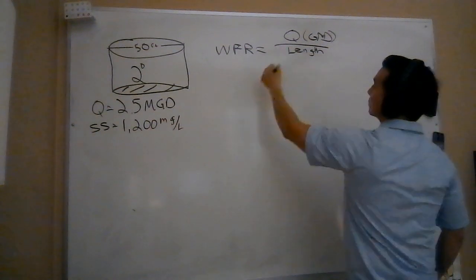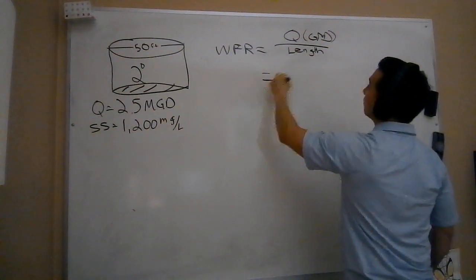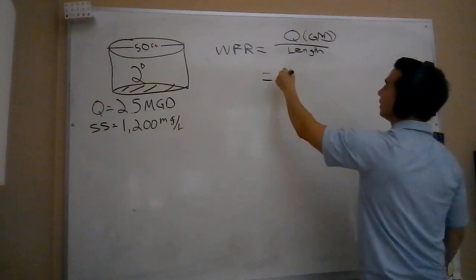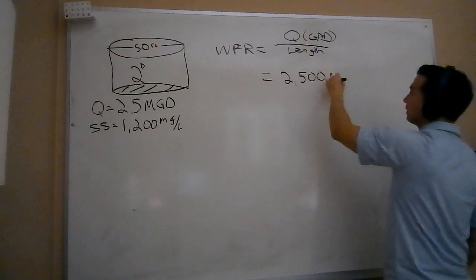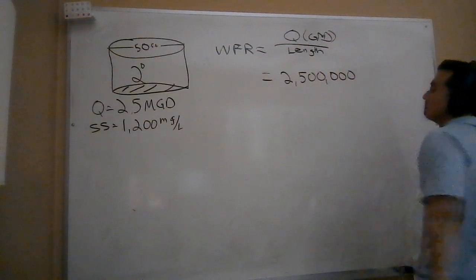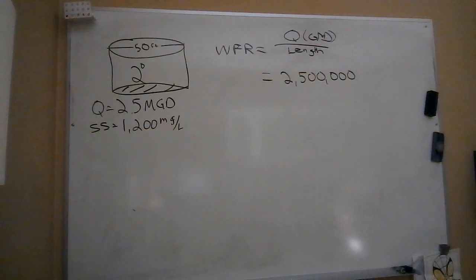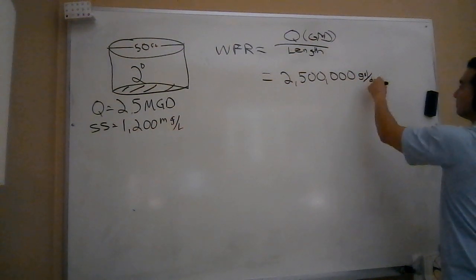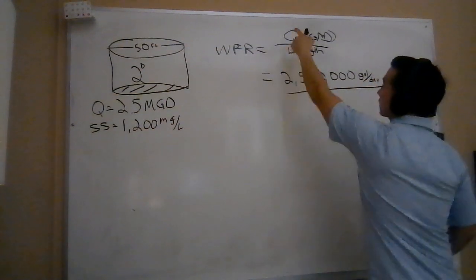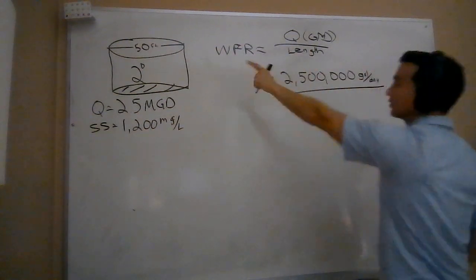My flow rate Q - I've already given that here - is 2.5 million. We're going to write that out all the way. With pounds formula, we like to plug it in as million gallons, but everything else we're going to write out in terms of gallons. So 2,500,000 gallons per day flow rate, and we're going to divide it by the length of my weir.